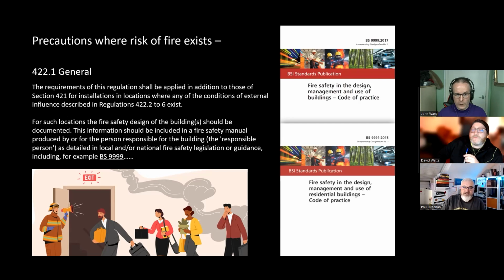So the requirements of this regulation should be applied in addition to those of 421 for installations and locations where, so 421 was AFDD, where the conditions of external influence in 422, so it refers to more regs. For such locations, fire safety design of buildings. This is a new thing post Grenfell. However, it isn't, because Part B of the building regulation has been out for decades. So has BS 9999. So of all these other standards that people have completely ignored or did not know existed. Okay, so fire design and fire engineering is, I've always said fire risk assessment is on an existing building, which it is under the reform order. Fire engineering is the application of all these principles and standards to something new to make things better.